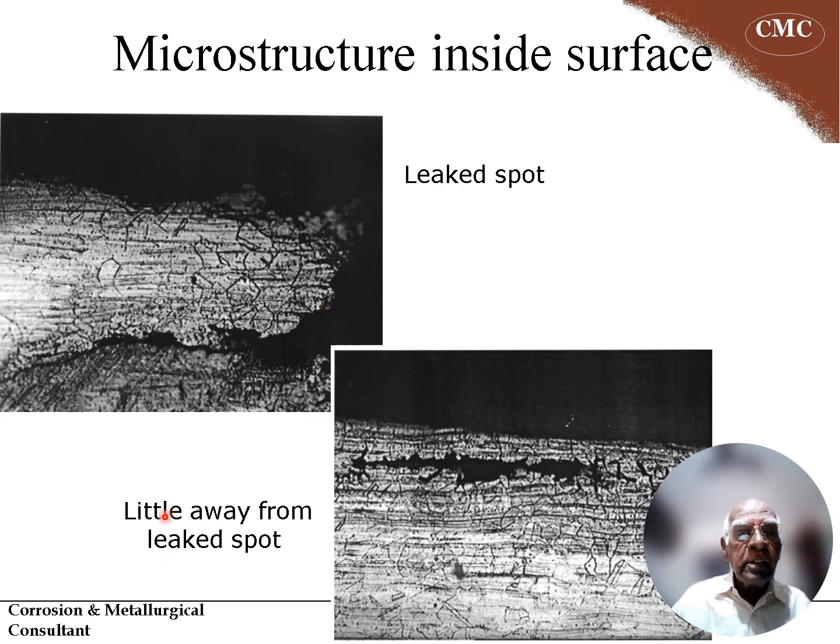Here on the same tube, a little away from the leaked spot, just to show the general microstructure of the tube itself, you can also see, to a certain thickness from the inside surface, the intergranular nature.